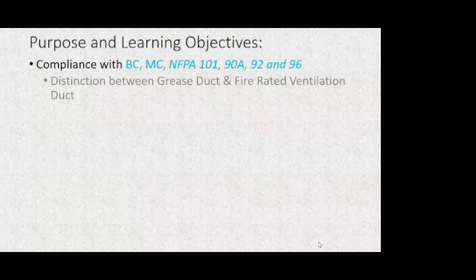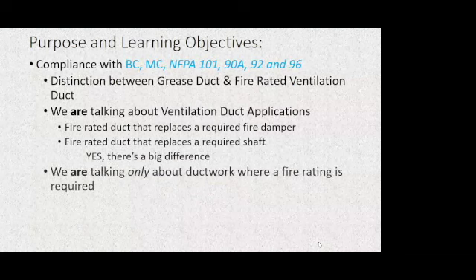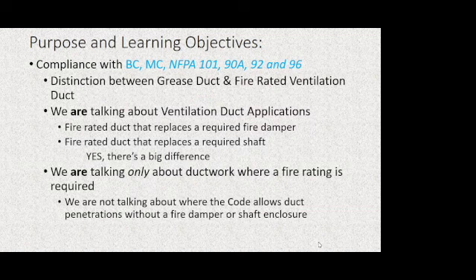And I think you'll agree that we have a problem in the industry of fire-rated duct products. The solution is not that hard, but it is harder than you might possibly imagine. So with that being said, we're focusing on the criteria in the state of Michigan codes as referenced. We're going to touch on building code, mechanical code, life safety code, and some of the NFPA reference standards therein. We will not be talking too much about grease duct, mostly in the sense of how we distinguish grease duct from the other fire-rated ventilation duct applications that are in the code.